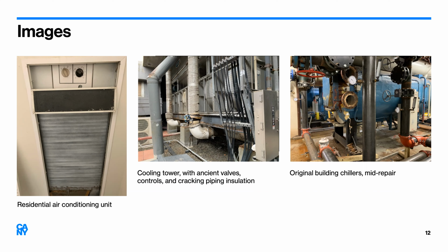The middle photo shows the cooling tower up on the roof. You can see that the water piping insulation is cracking. You can see that valve right in the middle of the photo - that's just a manual on-off valve. There's no modulating capability, and certainly no automatic capability. You can see the big on-off button off to the right, so there's no variable control for this - no variable speed for the motor or for the fans on this cooling tower. That lack of controls capability in older buildings is a real energy use driver, and frankly, a very easy way to upgrade the energy use of the building.